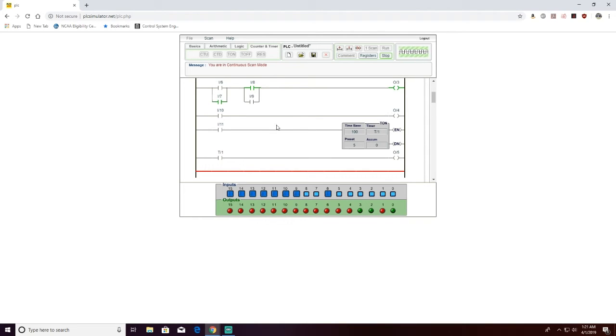Let's see. Next one is for just the car clearing the gate. So as long as the car clears the gate, it'll signal that the light can turn off and the gate can go back down. And timer is for any obstruction of the gate. So say the gate gets obstructed, input 11 turns on, the timer counts out for however long they would need it for, and brings that input high, which will bring another output high, which would more than likely trigger an alarm. And that's it.